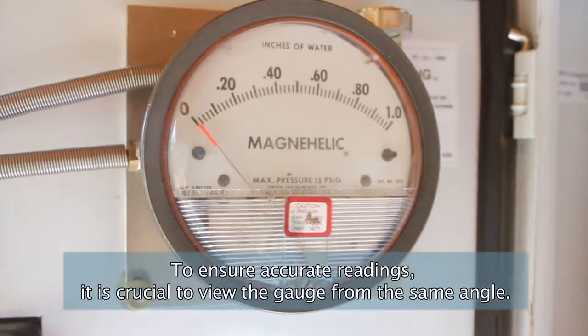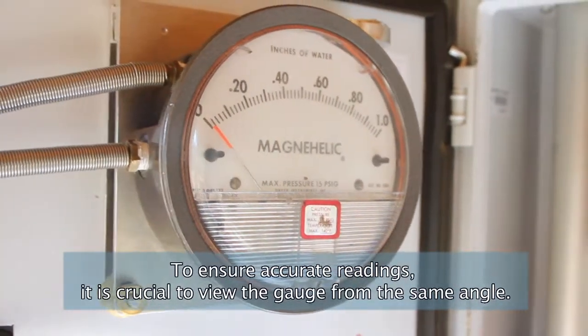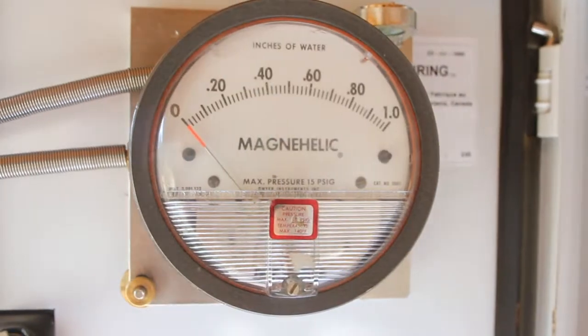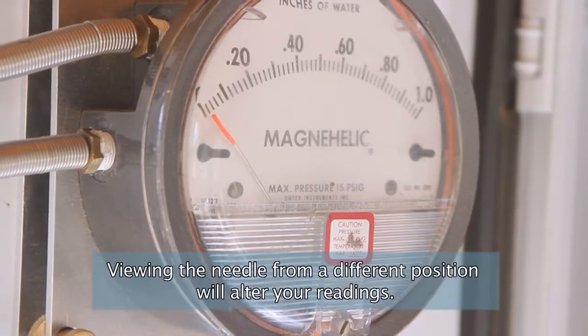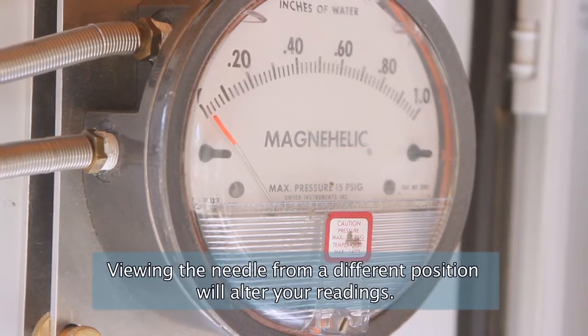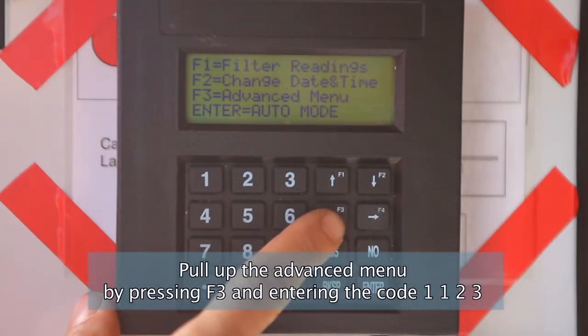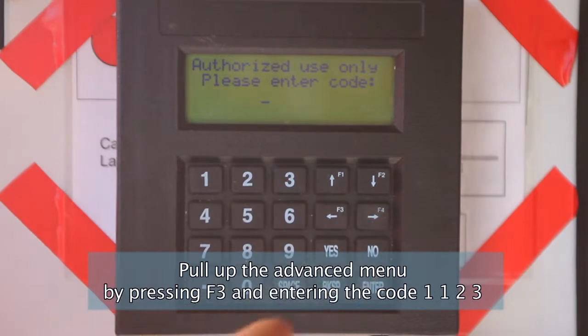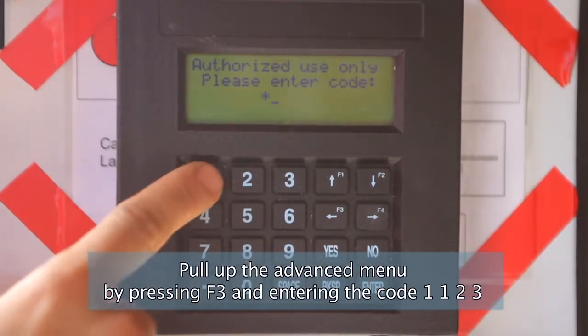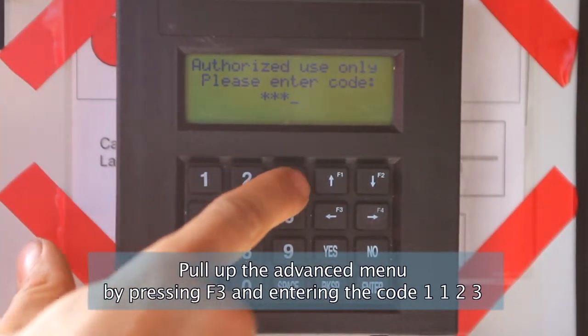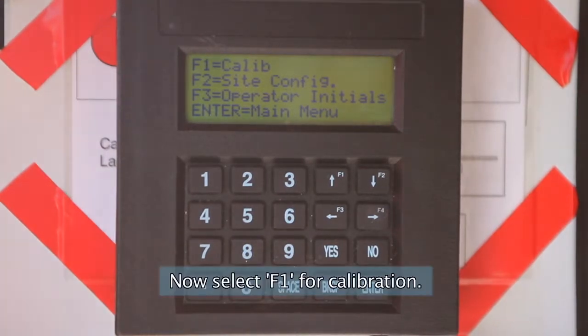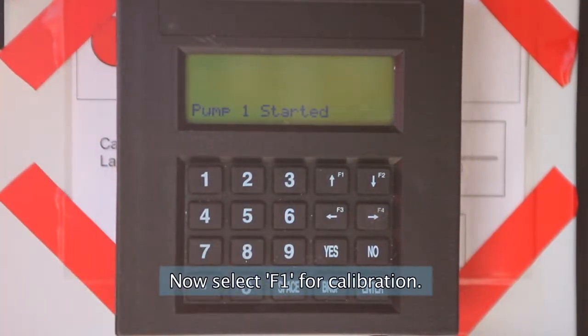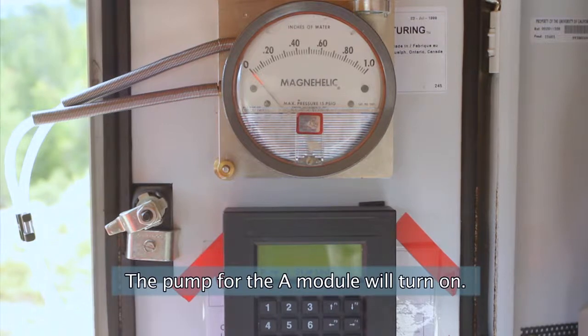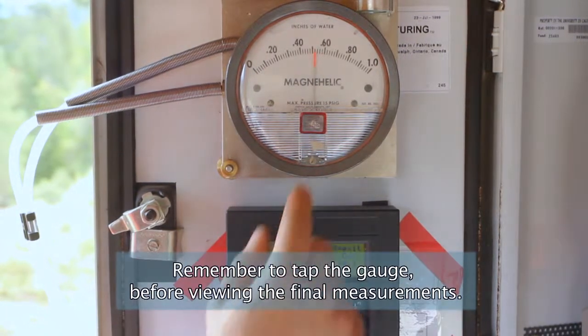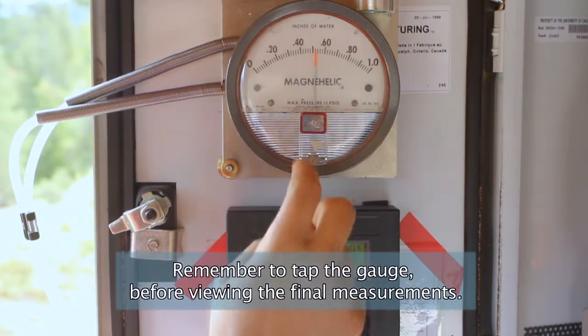To ensure accurate readings, it is crucial to view the gauge from the same angle. Viewing the needle from a different position will alter your readings. Pull up the advanced menu by pressing F3 and entering the code 1123. Now select F1 for calibration. The pump for the A module will turn on. Remember to tap the gauge before viewing the final measurements.